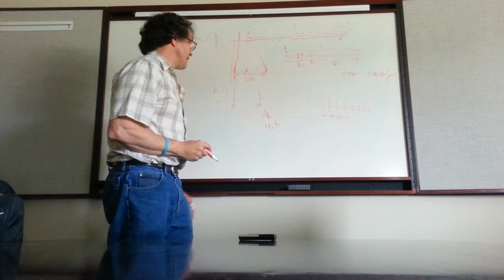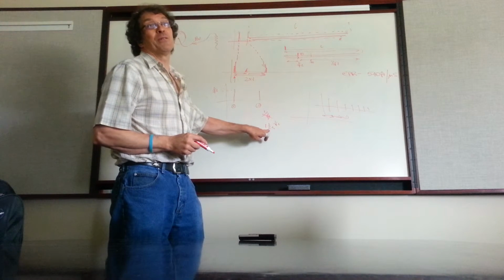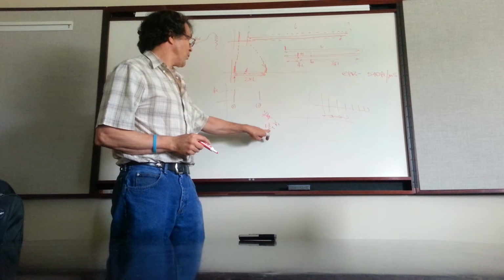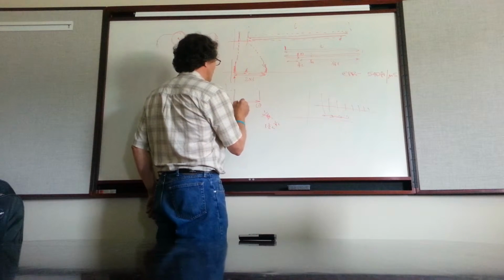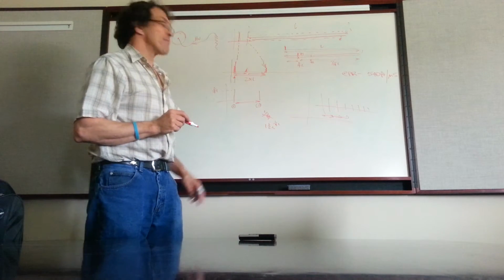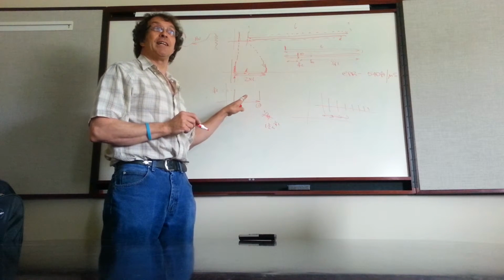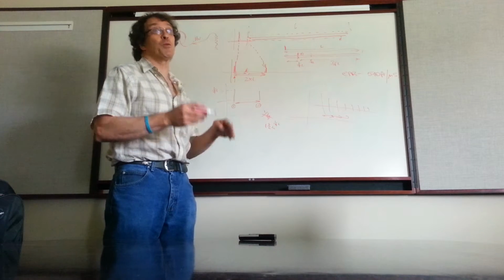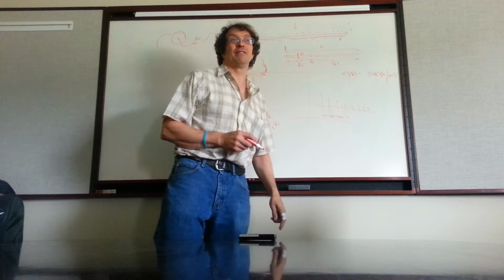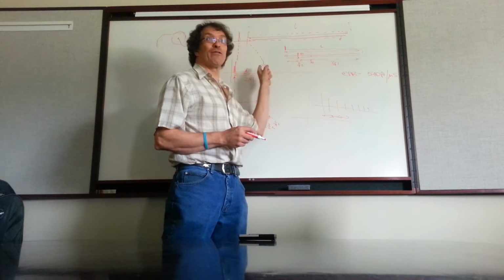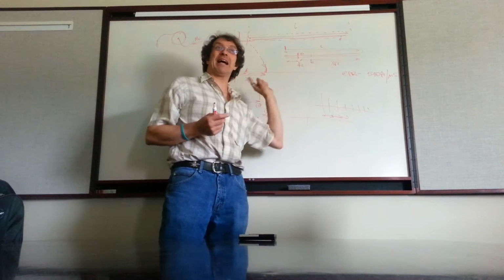What's half of 1.5? 3/4, right? So the distance you see on the screen, from here to that pulse, is twice the distance from the fault to the tail, not twice the distance from the fault to the front, because that pulse isn't coming to you, it's hitting the back end and coming back.